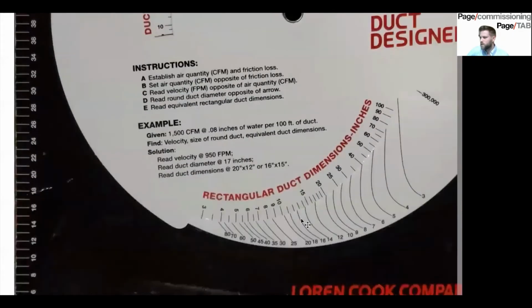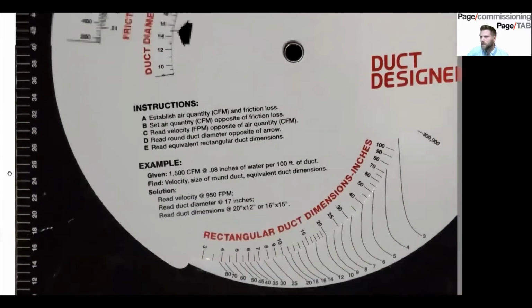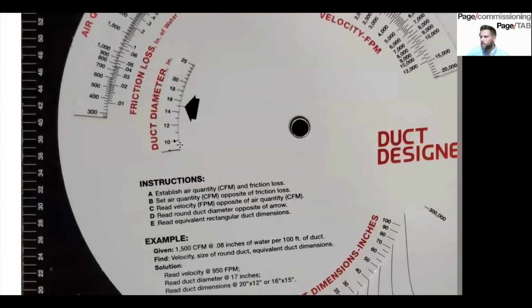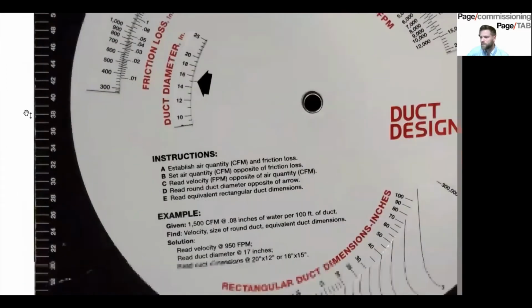And you can choose a rectangular duct from any one of these sizes. You just line them up. So a 6x40, usually you don't have a duct that thin and that wide, depending on your plenum space. But yeah, you could do a 20x10, or it determines what kind of duct diameter you need. So generally, if you're in the odd numbers, you want to go to the even. So then you would pick a 16 on this one.